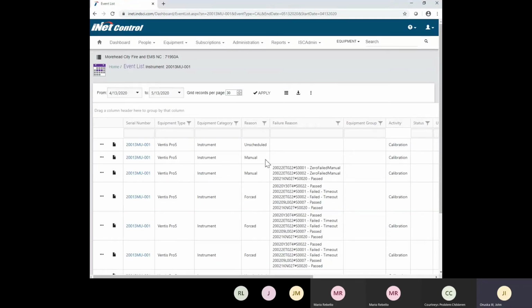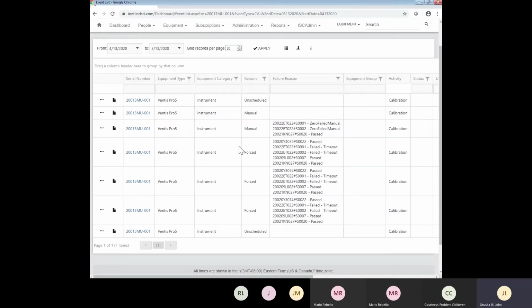Okay, so if I wanted to view all the calibration, here we go. Here's all the calibrations. And right here we could see a manual calibration. Manual calibration is going to show up every time you zero the instrument. Okay, because as I said, it comes up and it says, hey, this is a calibration of the O2 sensor. So it registers it as a manual calibration.